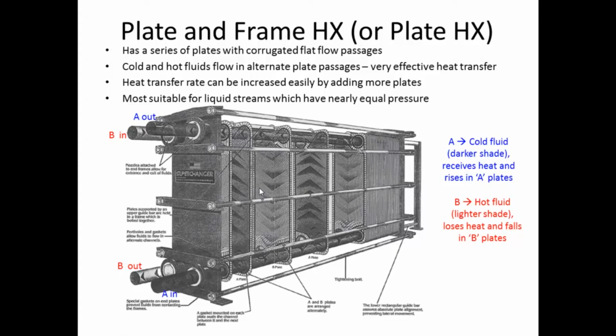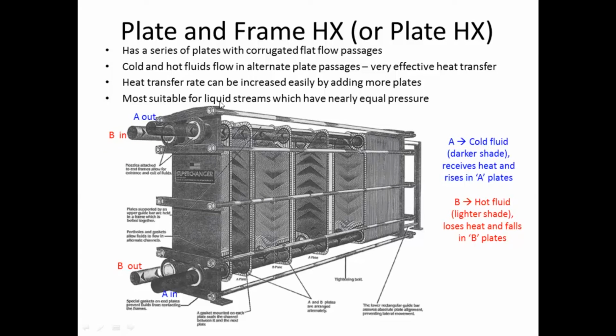One benefit of the plate and frame heat exchanger, apart from its compactness, is that it is of a modular nature. We can increase the heat transfer by adding more plates. We can always extend this further to increase the heat transfer. And this is most commonly used for liquid streams which have nearly equal pressure.